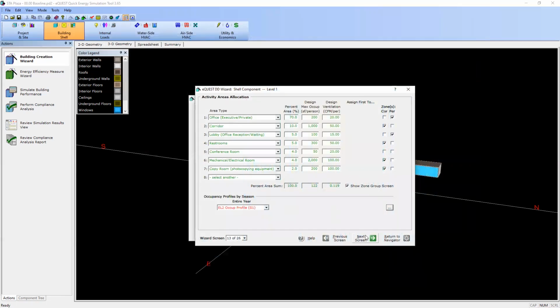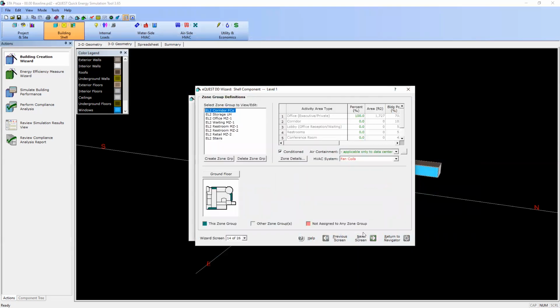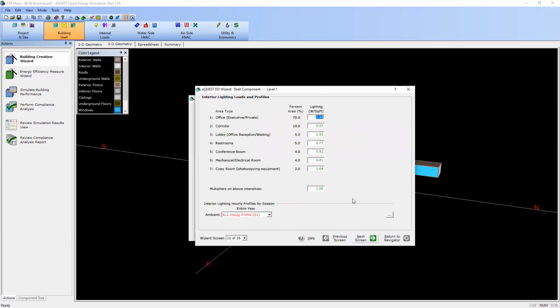And they do similar profiles for things like lighting and miscellaneous loads like computers. Here you can define what types of spaces you have: what spaces are offices versus corridors, restrooms, conference rooms, and also which HVAC system each of those spaces happens to be on. You can plug in some lighting watts per square foot loads, and they have some defaults built in for these various space types because sometimes you don't really know. And sometimes you just have to do a best guess.